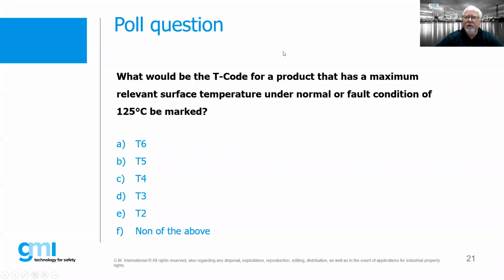So yes, the majority of you did get the correct answer, and the correct answer is T4. So remember what T4 is, it's 135 degrees C. That means if I have a product that during my testing under a normal or fault condition in its highest ambient, the relevant surface does not exceed 125 degrees C, which is below T4, that's the way we would mark our product. So the product would actually have a T4 rating on it, and that product would then be suitable for environments in which you require either T4, T3, T2, or T1 gas groups, if you will, or ignition temperatures of gases. So we're below the ignition temperature of all T4, T3, T2, and T1 gases. So good job. Now, let me close that.